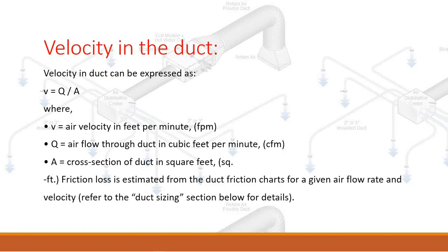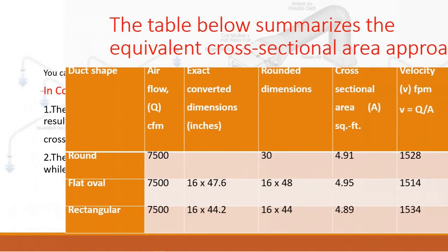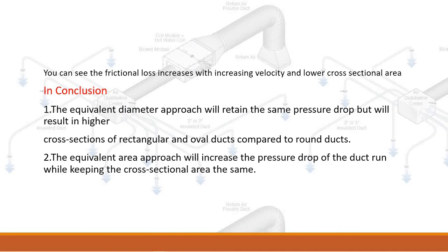Velocity in the duct can be expressed as V = Q / A, where V equals air velocity in feet per minute (FPM), Q equals airflow through the duct in cubic feet per minute (CFM), and A equals cross-section of the duct in square feet. Friction loss is estimated from the duct friction charts for a given airflow rate and velocity — refer to the duct sizing section for details. The table summarizes the equivalent cross-sectional area approach. Frictional loss increases with increasing velocity and lower cross-sectional area.